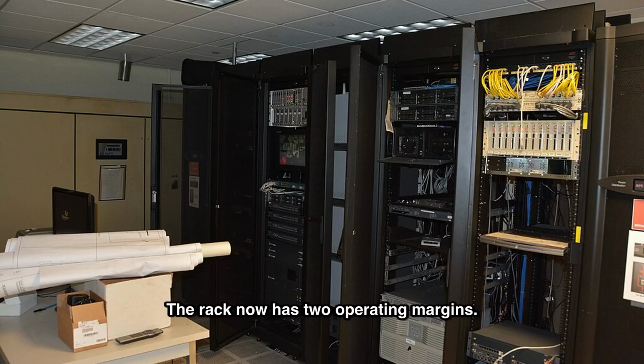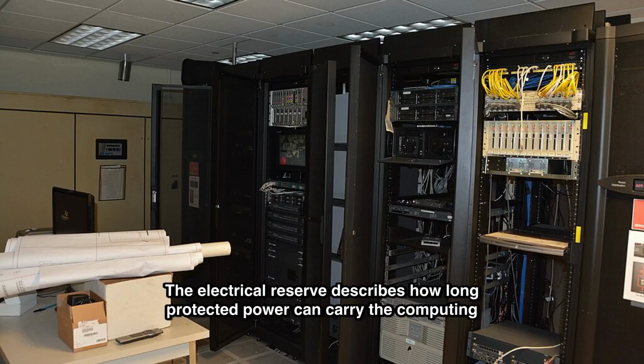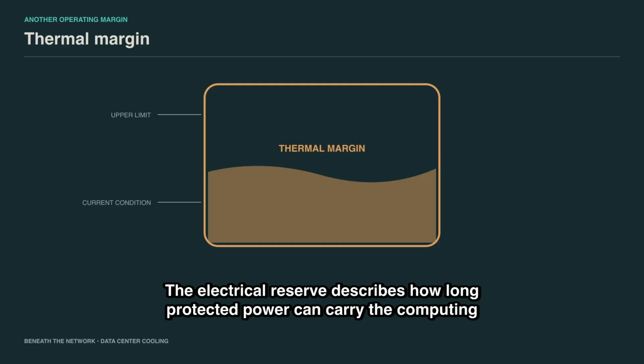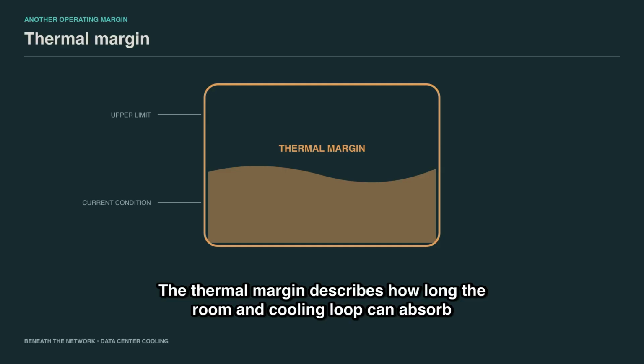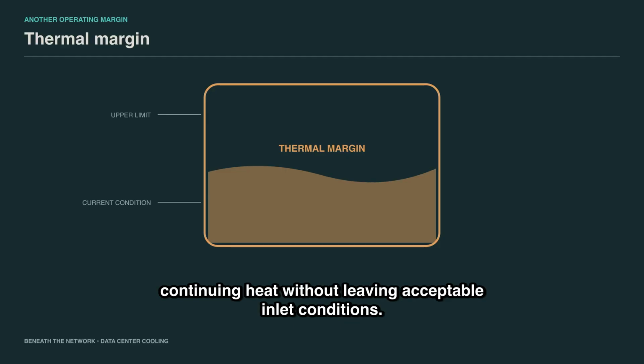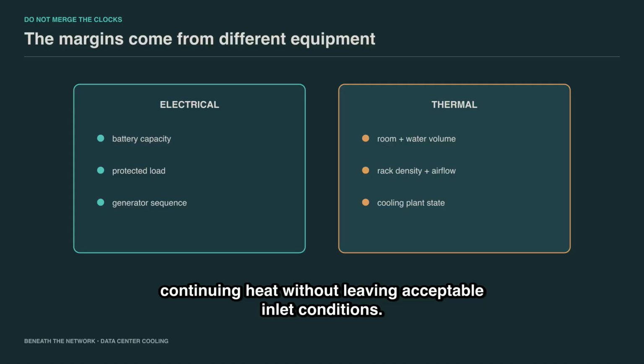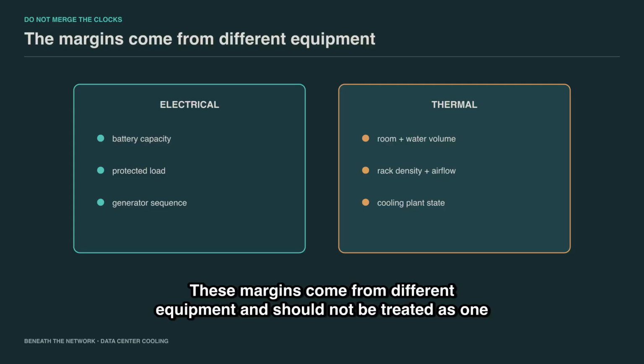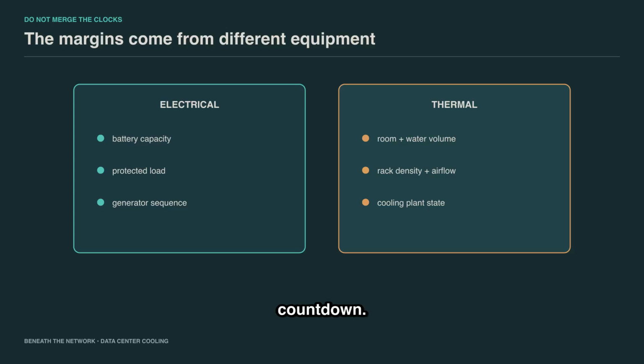The rack now has two operating margins. The electrical reserve describes how long protected power can carry the computing load. The thermal margin describes how long the room and cooling loop can absorb continuing heat without leaving acceptable inlet conditions. These margins come from different equipment and should not be treated as one countdown.